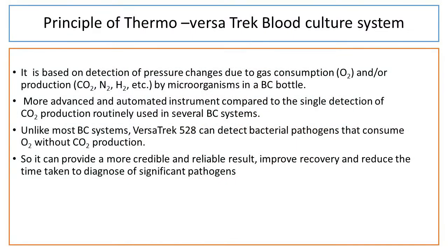The principle of the Thermo VersaTREK blood culture system is based on the detection of pressure changes due to gas consumption — O2 — and/or production — CO2, N2, H2, etc. — by microorganisms in a blood culture bottle. It is a more advanced and automated instrument compared to single detection of carbon dioxide production routinely used in several blood culture systems. Unlike most blood culture systems, the VersaTREK can detect bacterial pathogens that consume oxygen without CO2 production, providing more credible and reliable results, improving recovery, and reducing time taken to diagnose significant pathogens.